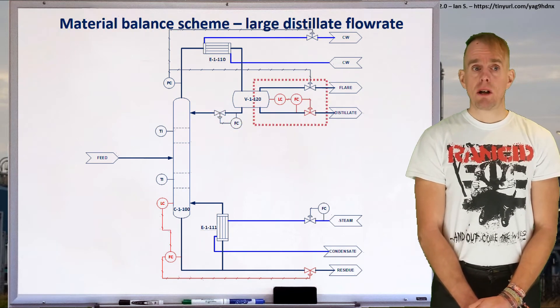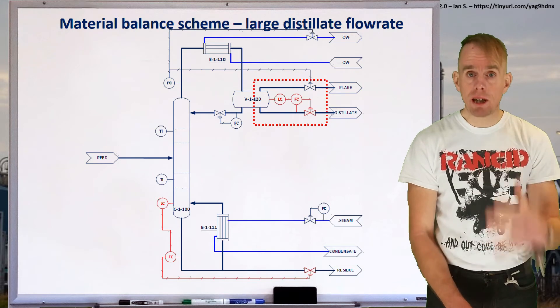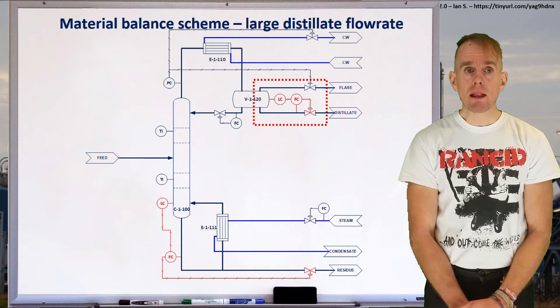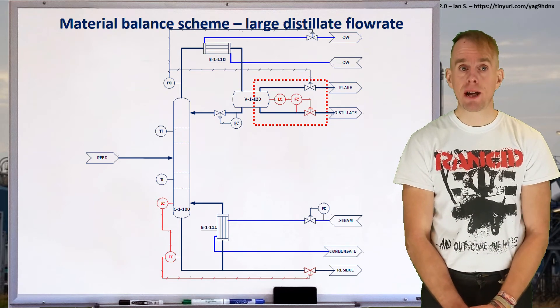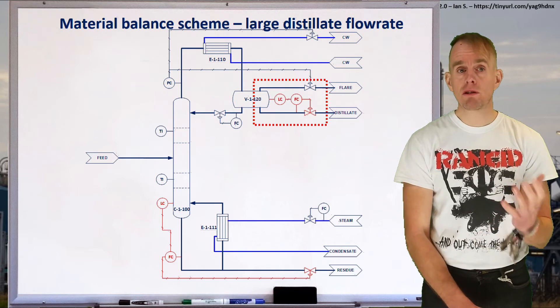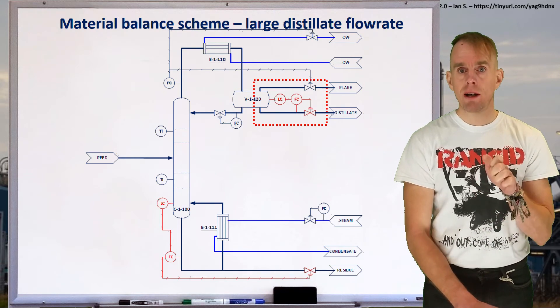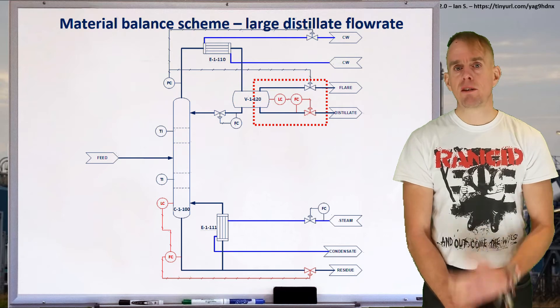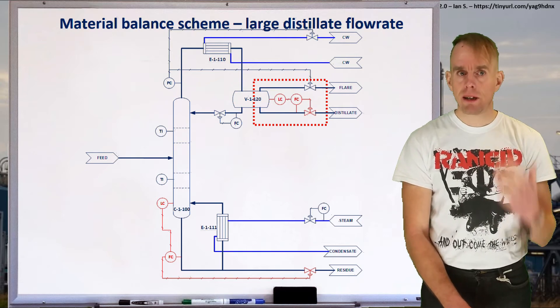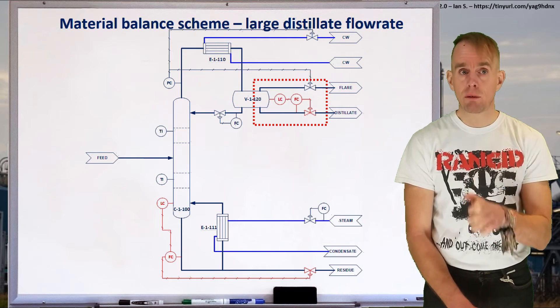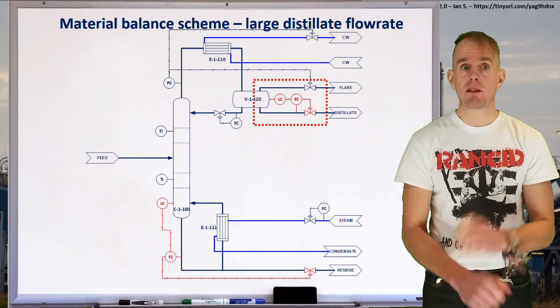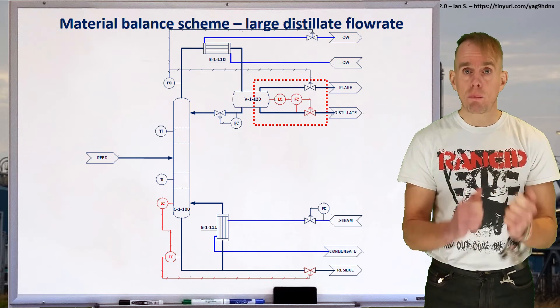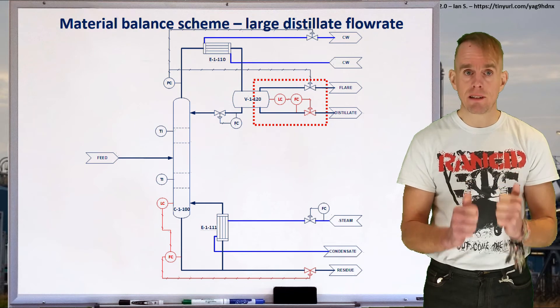If we've got a large distillate flow, we don't change what's happening in the base of the column at all — we keep the level control on the sump cascaded onto the residue flow rate. The dashed red box shows what has changed. If we've got a large distillate flow rate, we simply swap the control onto the flow that's going to be the most sensitive — the larger flow is the easiest to control. Now I have my level controller for the reflux drum cascaded onto the flow controller for the distillate outlet, and the reflux ratio is set by knowledge of that distillate flow, with the reflux return flow controller operating on whatever ratio is selected.